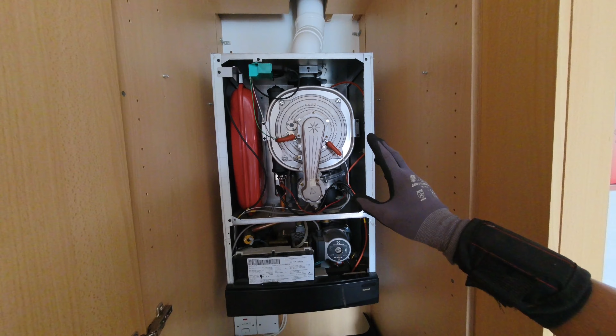A little tip for when putting these in service mode, if you've got a small circuit like over here, where it's all underfloor heating, so it's getting up to temperature too quickly. What I tend to do is, it's a bit difficult to see because it's dark, but you've got the Hall effect sensor which sits on the flow turbine at the back there. Pop that off. That sensor is, where is it? There it is. So pop that sensor off, and also take off the diverter actuator.